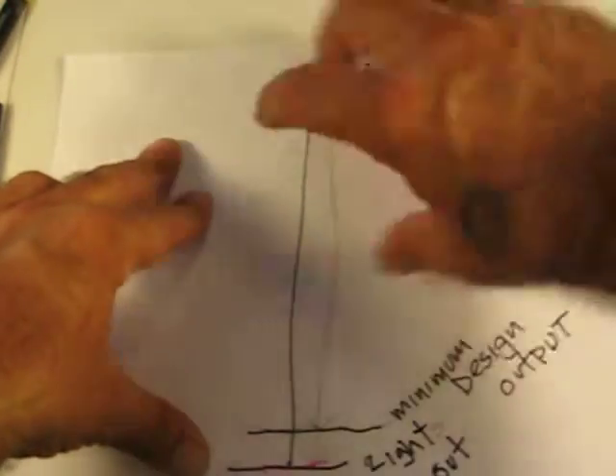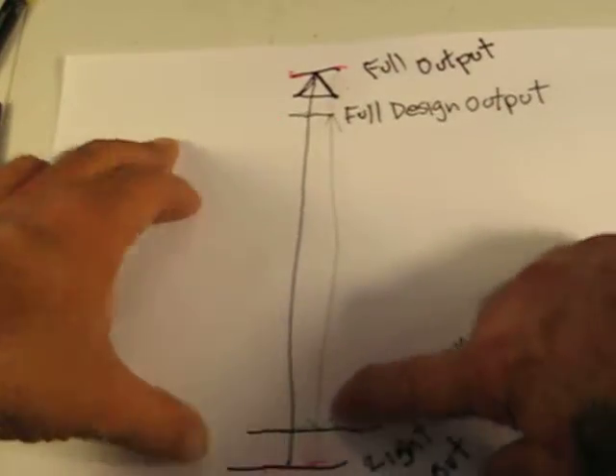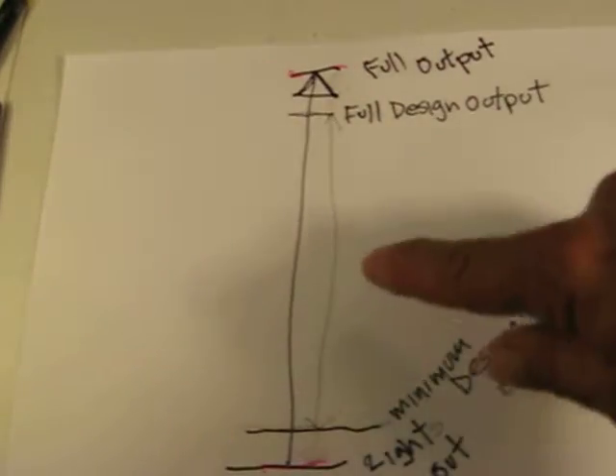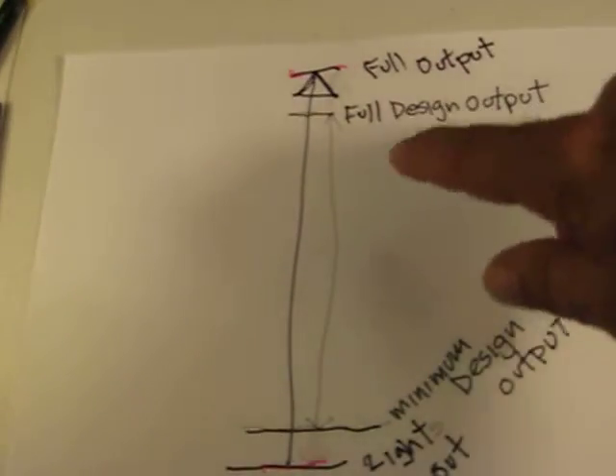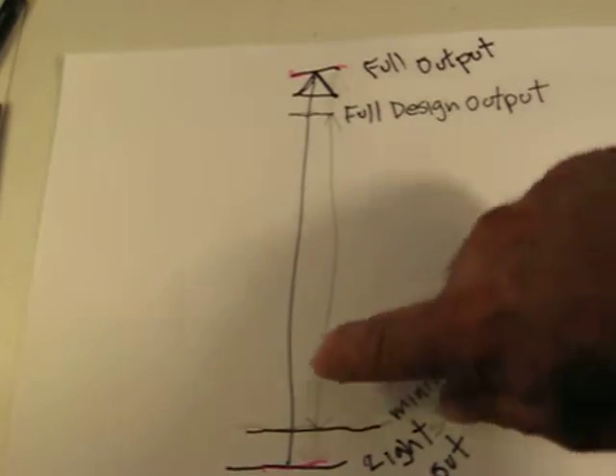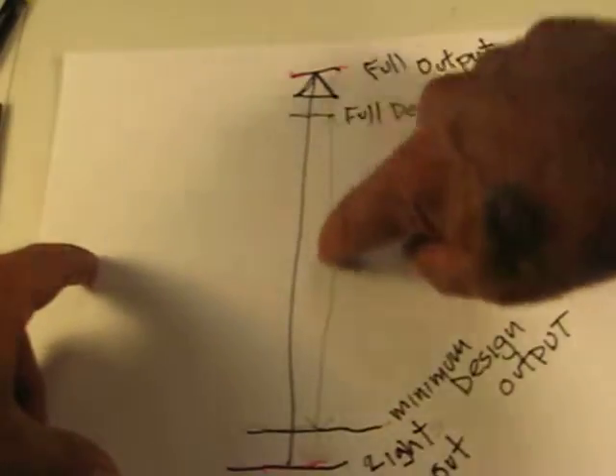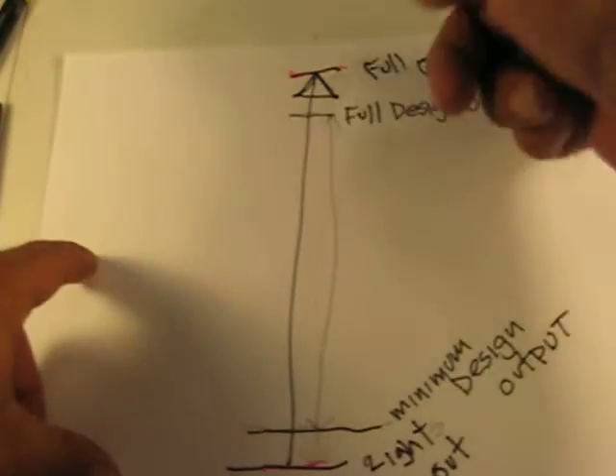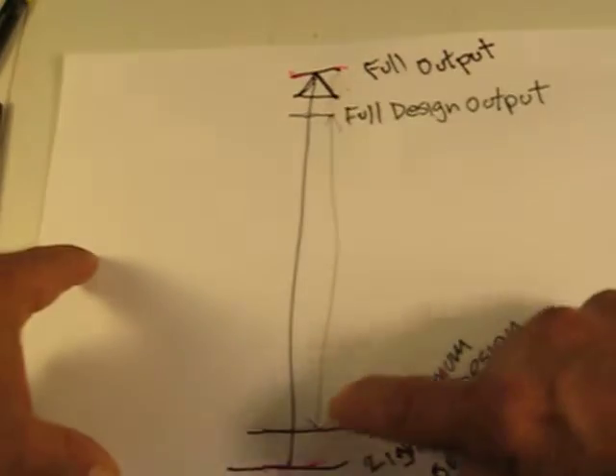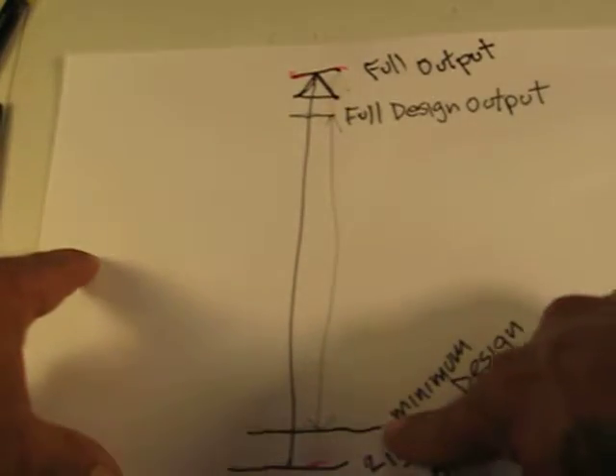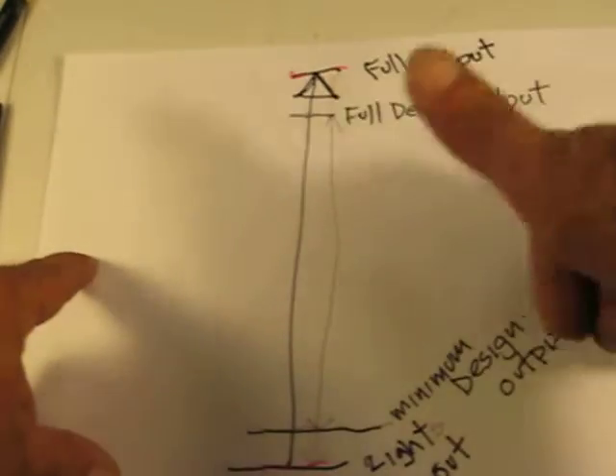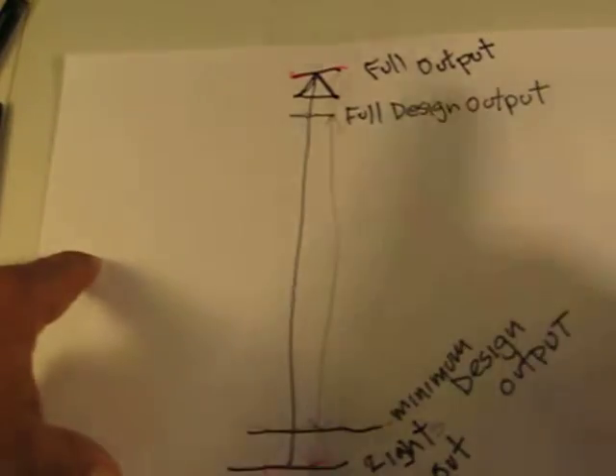If you have a dimming slider or rotating button, which is required in many cases and in many areas, it has to be able to dim between full design output — where they put a hard cap — and minimum design output, and of course click-click on-off.